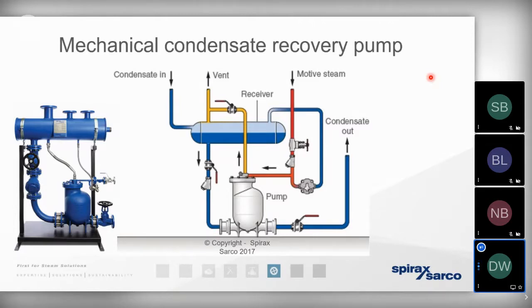But the thing to bear in mind is this pump, it will cycle. So it'll generally discharge 4 or 5 times an hour, maybe, meaning that we do need to size the downstream condensate pipework on the discharge rate of the pump and not on the filling rate of the pump. So that means that this pipework here could be sized 3, maybe even 4 times bigger than the condensate filling pipework. So if you're comparing the infrastructure from an electrical to a mechanical pump, could well be that the infrastructure is going to be more expensive for a mechanical pump because of that greater pipe diameter that's required.